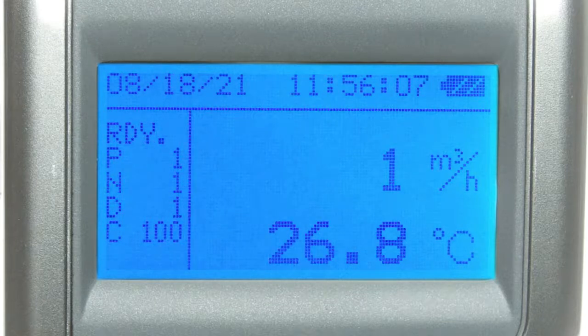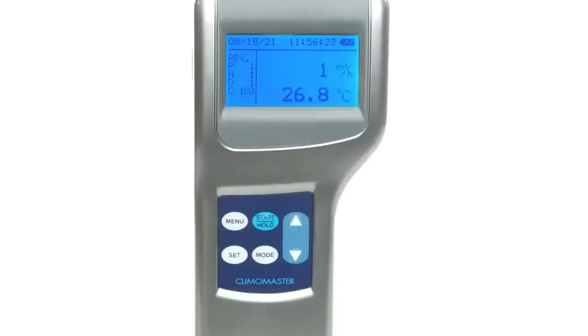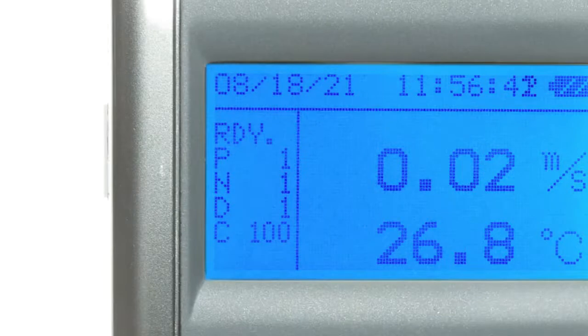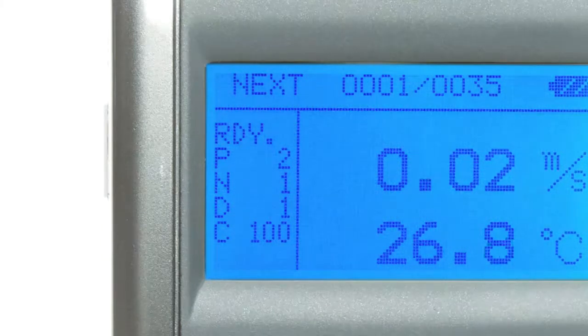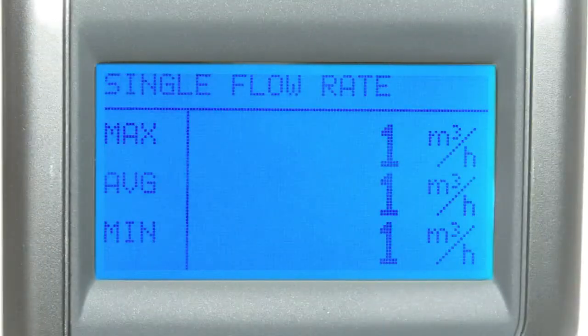If you need to change parameters before starting the measurement, you can use the navigation buttons and Set button to do so. The P stands for current number of points, the N stands for current number of samples, the D stands for the selected duct entry number, and the C or R stands for the duct shape and size. To stop the measurement, press Start or Hold. To continue measuring, press it again. And to complete the measurement, press Set. Then the results will be displayed. If point 1 is not completed, you won't see results displayed on the screen. Pressing Menu will complete the measurement without storing data.